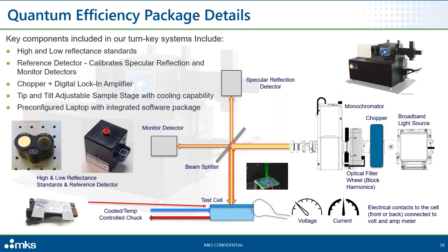This also includes the tip and tilt adjustable sample stage that has cooling and vacuum chuck capability, so you can hold your device and cool your device right off the bat with this turnkey system. And as mentioned, this comes with a pre-configured laptop with all the integrated software package pre-installed, the files ready to go, so you can start doing QE scans right out of the box.